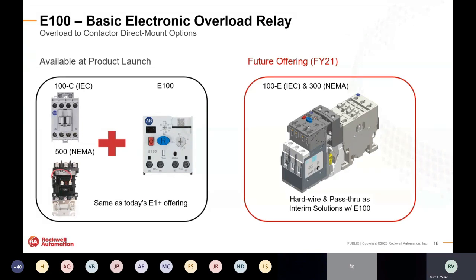One thing I'd like to draw your attention to: today the E100 already supports direct mounting with the Bulletin 100C and Bulletin 500 contactors. We're working on a project this fiscal year to also support the newer Bulletin 100E and 300 contactors. By the end of next year, the E100 will offer a direct mount solution to those newer style contactors as well. However, if you wish to use the E100 overload with the newer contactors now, as an interim solution you can hardwire them or use the pass-through version temporarily until the direct mount is available.